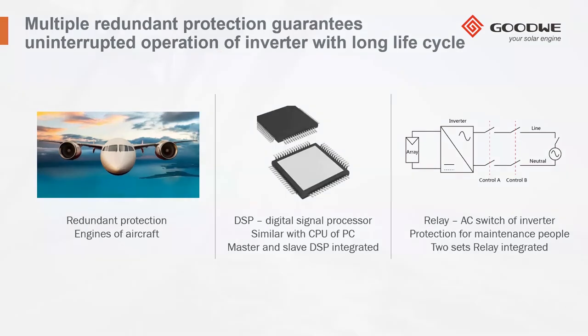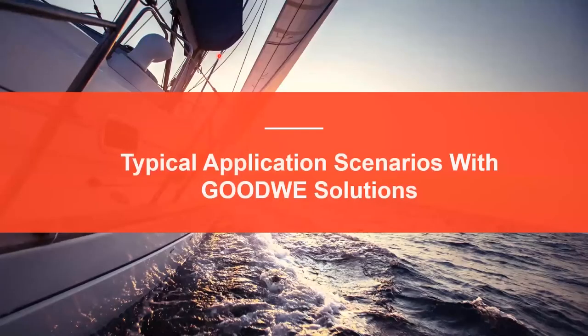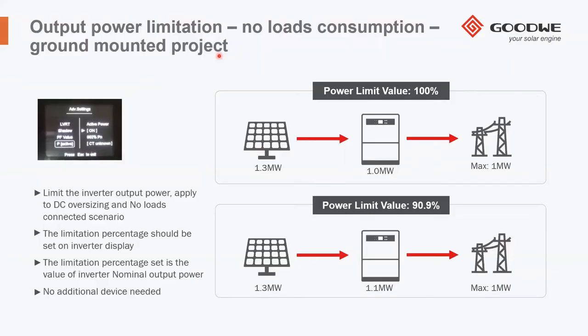The typical application scenario with the GoodWe inverter, as an example, we can have this situation. I'm not sure this is very common in Greece, but in other markets it's extremely common, which is the requirement for the limitation of the output power. In this case, as an example, when you have no load consumption, for example a ground-mounted project, you can set the power limit, and then you can match the requirement given by the grid operator, which says I can only accept 1 mega as an input. Then you can easily play with the power limit value and the PV input value of your modules to adjust the functioning of your system in order to match the requirement of the grid operator.